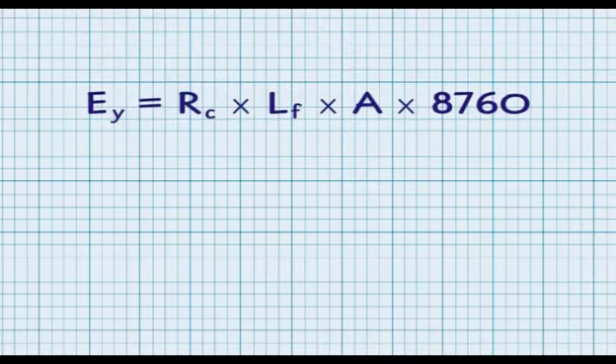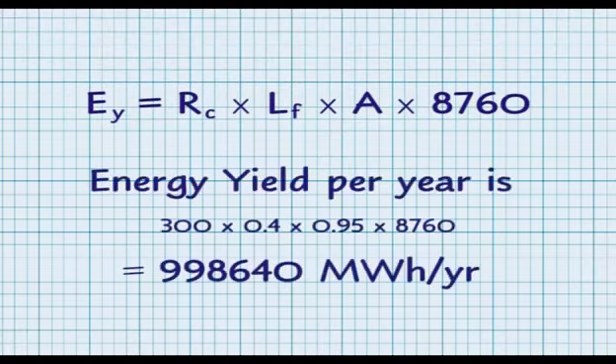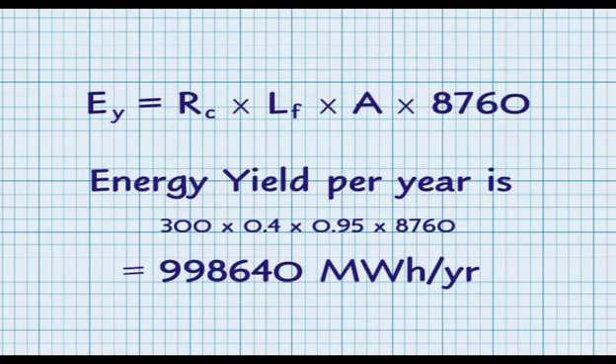If we put this into an example, we have a wind farm with a rated capacity of 300 megawatts, a load factor of 0.4, and an availability of 0.95. These are typical values for offshore wind farms. When you put this into the equation, we come out with a figure of 998,640 megawatt hours per year.